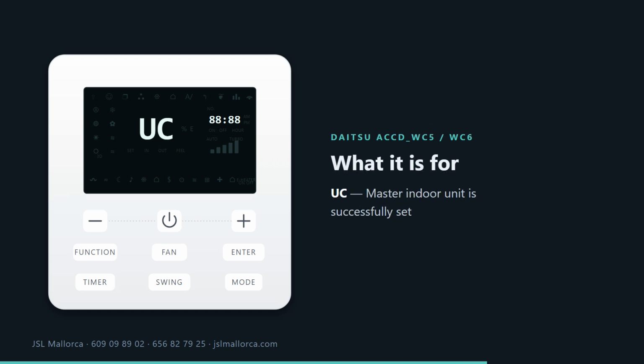Code UC. According to the manufacturer, master indoor unit is successfully set. Code UD. According to the manufacturer, grid connection driver board error. Code UE. According to the manufacturer, refrigerant charging is ineffective.